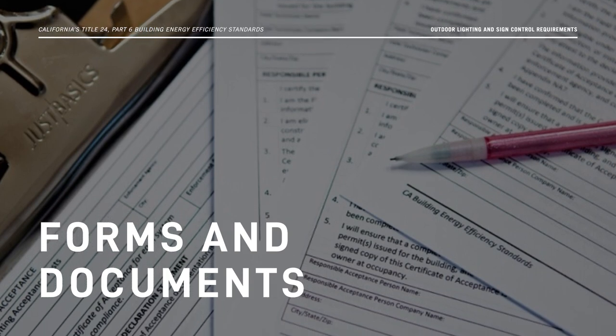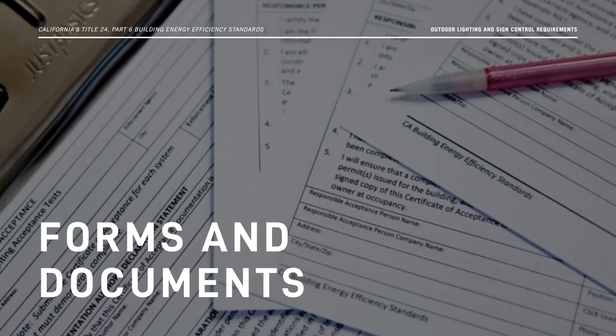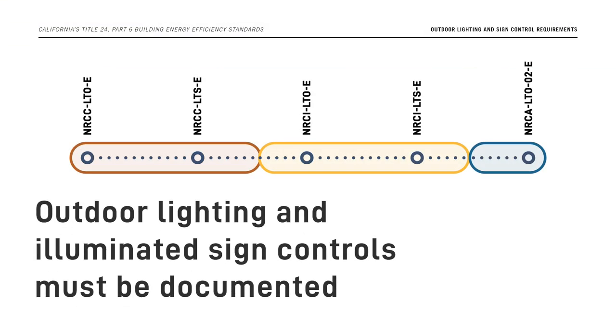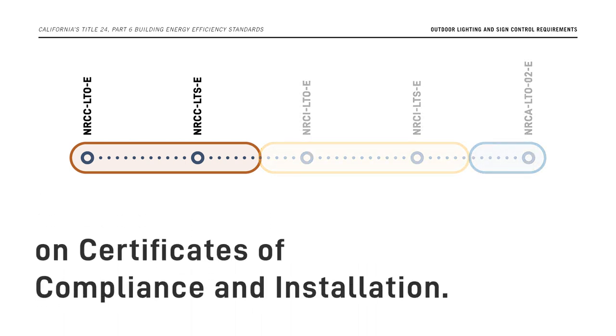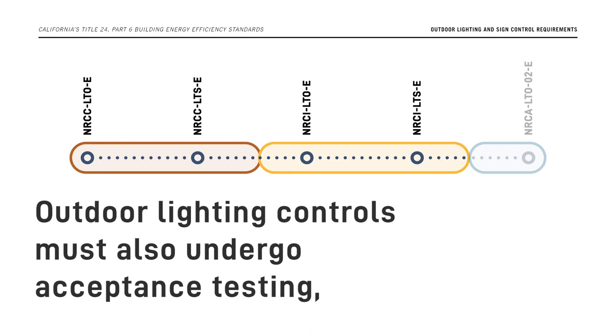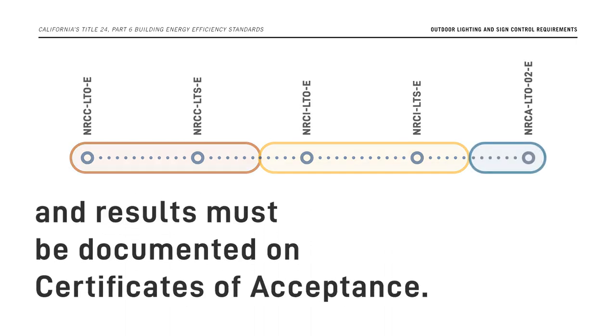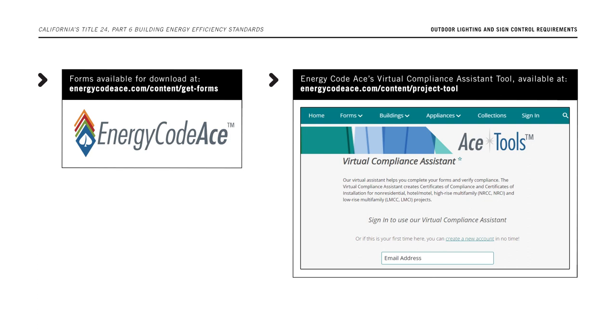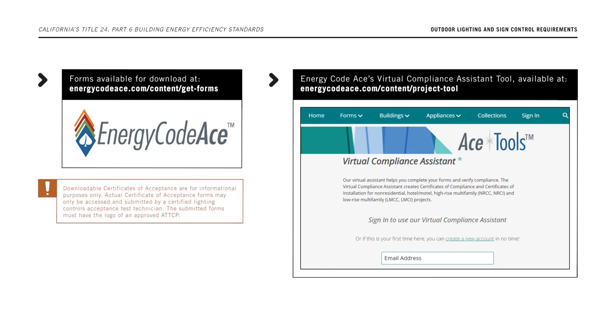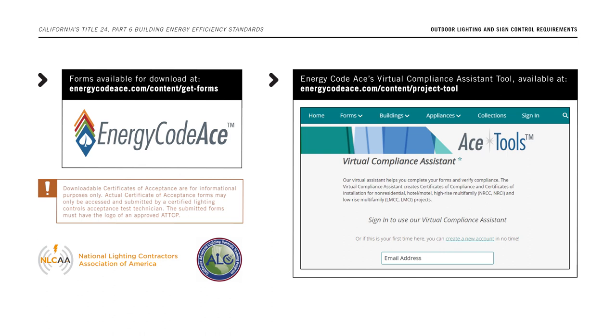We'll now discuss the certificates or forms needed to demonstrate Energy Code compliance to your local enforcement authority. Outdoor lighting and illuminated sign controls must be documented on certificates of compliance and installation. Outdoor lighting controls must also undergo acceptance testing and results must be documented on certificates of acceptance. All certificate of compliance and certificate of installation forms are available using Energy Code ACE's virtual compliance assistant tool at www.energycodeace.com/content/project-tool. Certificate of acceptance forms may only be accessed and submitted by a certified lighting controls acceptance test technician, and the submitted forms must have the logo of an approved acceptance test technician certification provider, or ATTCP.